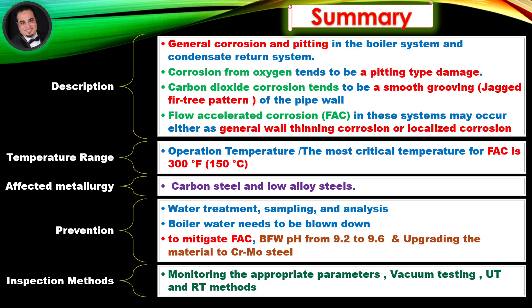Temperature range: the most critical temperature for flow accelerated corrosion is 300 degrees Fahrenheit. Affected metallurgy: carbon steel and low alloy steels. Prevention: water treatment, sampling, and analysis. Boiler water needs to be blown down to mitigate flow accelerated corrosion. BFW pH from 9.2 to 9.6 and upgrading the material to chromium molybdenum steel are recommended.